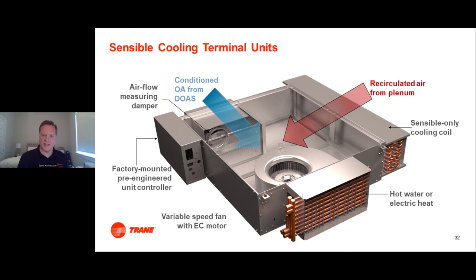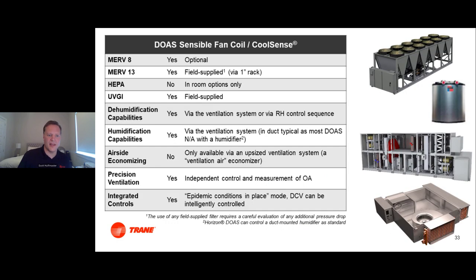The other piece to this is these systems are designed to have humidity sensors, and we're going to watch very closely the latent loads in the space so we can reset the dehumidification levels from our DOAS unit. They are decoupled, sensible and latent designs. That drip pan there is actually not piped because it's going to have just a sensor. So if you really review a system like this, now you've got this system that can really deliver on a lot of these things. There's some big cost advantages to it.